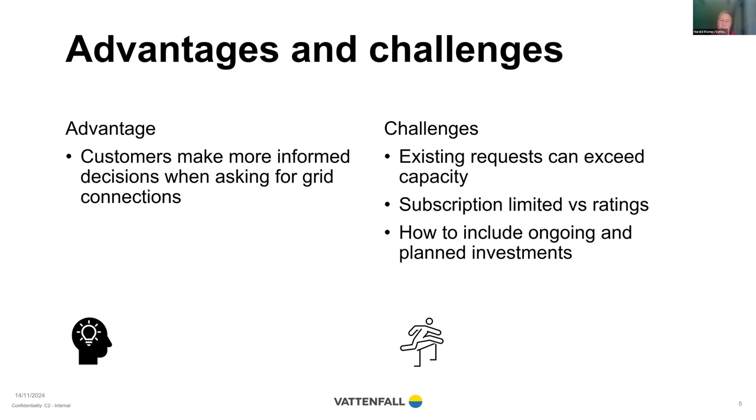Also, we have subscriptions between different voltage levels, so that can be a limit, and you might not have the actual rating limitations. And then also how to include ongoing investments and planned investments in your capacity calculations. These are considerations you need to make when you present the capacity calculations.